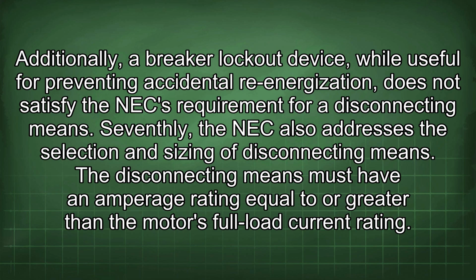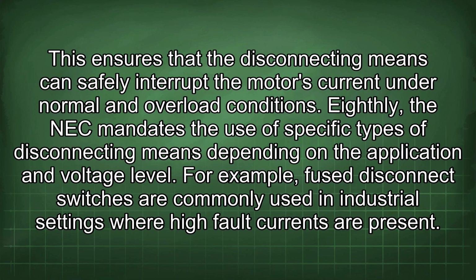Seventhly, the NEC also addresses the selection and sizing of disconnecting means. The disconnecting means must have an amperage rating equal to or greater than the motor's full load current rating. This ensures that the disconnecting means can safely interrupt the motor's current under normal and overload conditions.